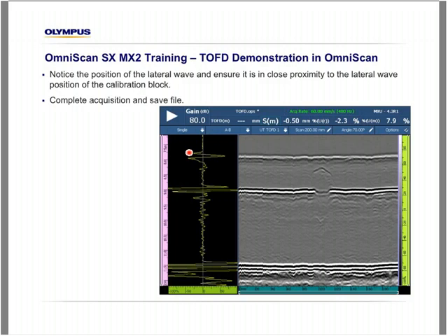The overwhelming majority of new TOFD users don't go to that extent to define the PCS and wedge delay initially, and it hurts them in their depth and height sizing after the inspection. It does not hurt them in detection and length sizing generally.